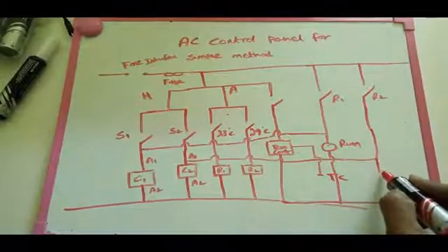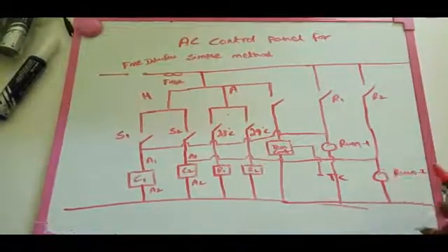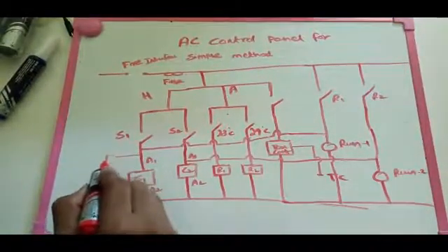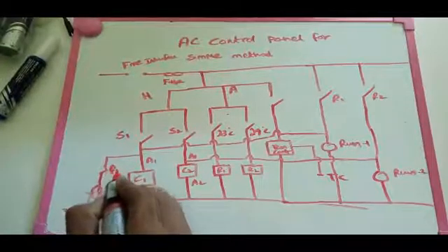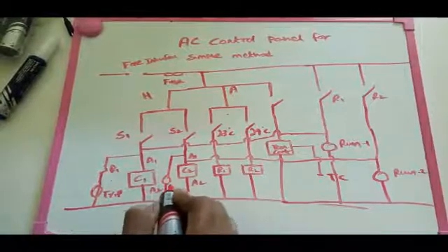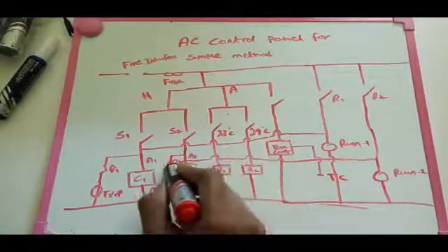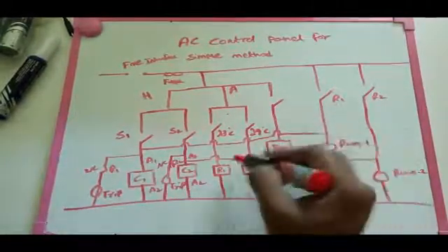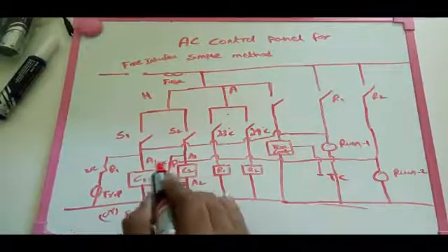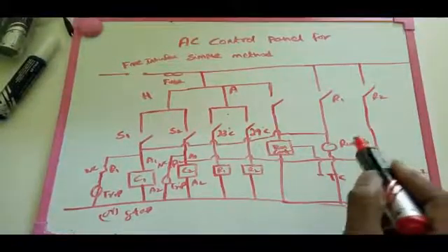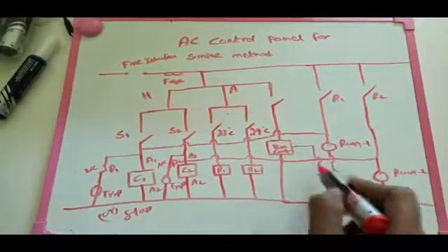We also need to add run and stop indications for AC1 and AC2. The run indication uses the NO contact of the relay or contactor. For the stop or trip indication, we use the NC contact of contactor C and the NC contacts of relay 1 and relay 2. This is the complete method to control two ACs based on the temperature controller and thermocouple. If you have any doubts, please comment. Don't forget to like and share this video.